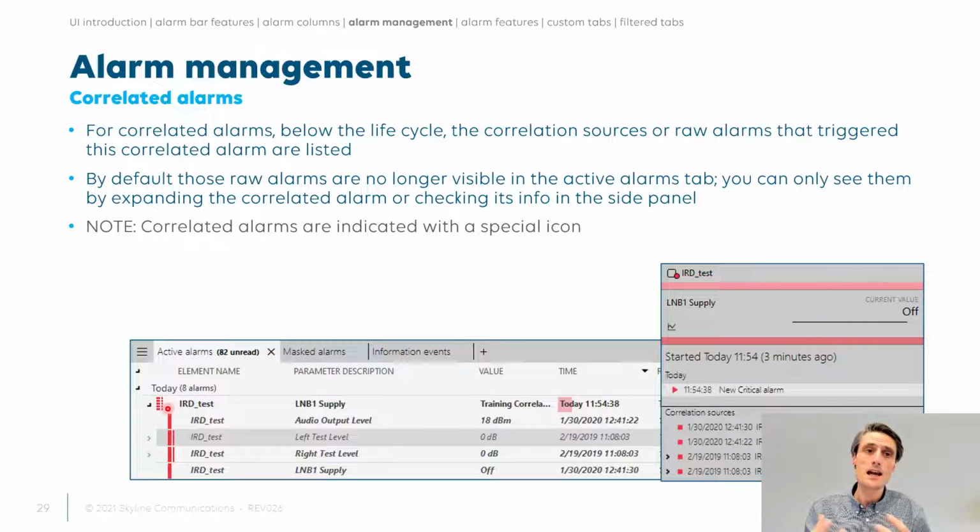So the correlation engine has certain detection mechanisms to detect certain patterns in your system, and it can react on that. So it detects something and then it takes some action, which could be, for instance, going to a backup element or executing some automation scripts, notifying somebody, or generating a correlated grouped alarm, nicely combining all of the raw element alarms into one single meaningful alarm for the operator, so that I only see one alarm instead of 10 different alarms.